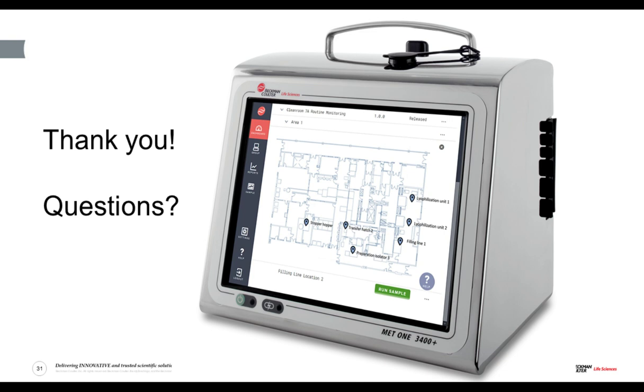Your next question: you showed a remote review and approve feature for the MET ONE. What software is required to access the counter remotely, and how do you guarantee security? In fact, you don't need any software to access the counter remotely. As long as the counter is connected to your company network, you can control SOP versions and review and approve data from your office simply using a web browser such as Google Chrome. Security is assured as the user who logs on remotely must use their Microsoft Active Directory-controlled username and password via the web browser interface in order to browse the counter remotely.